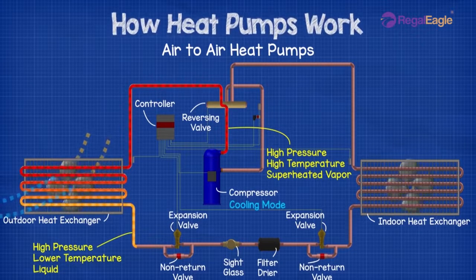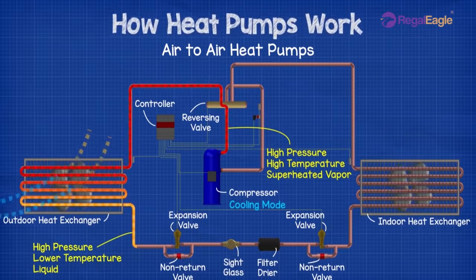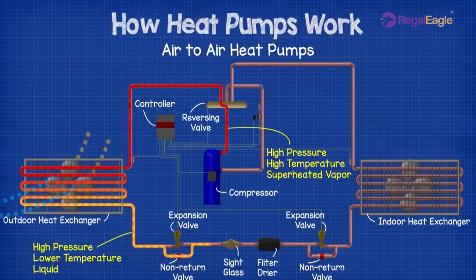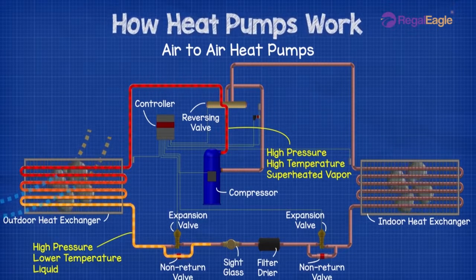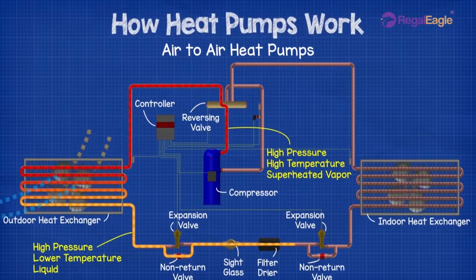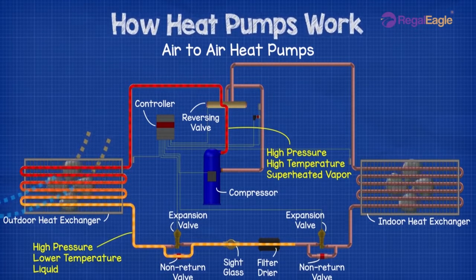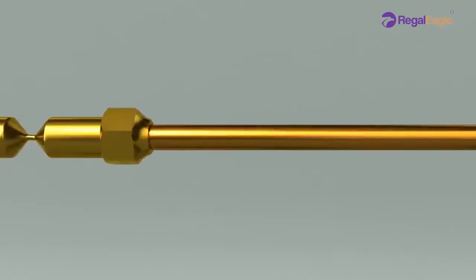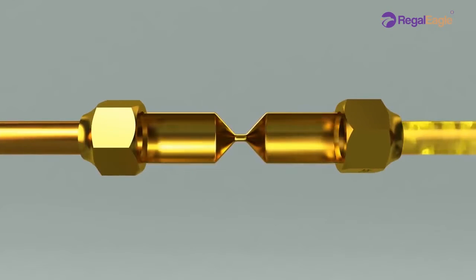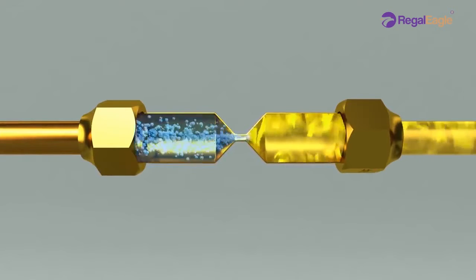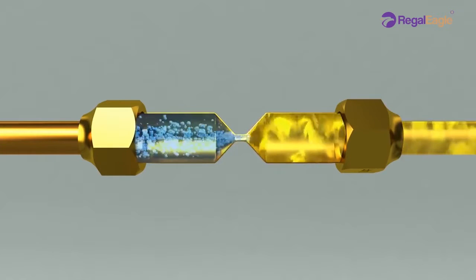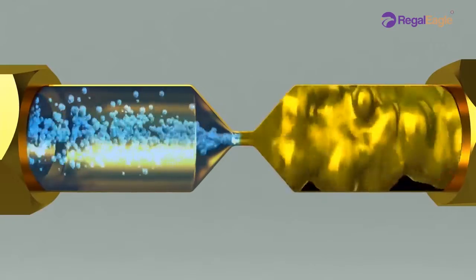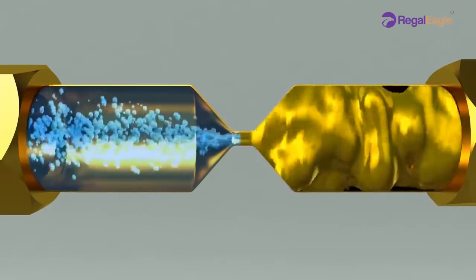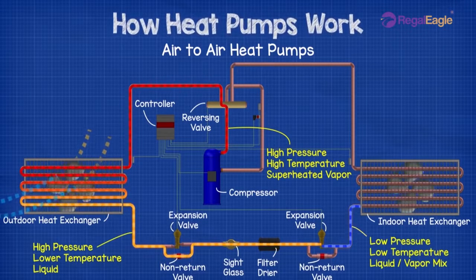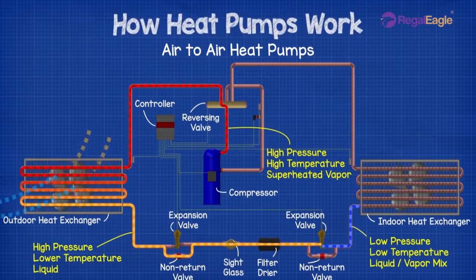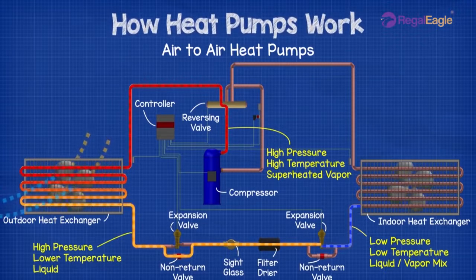The refrigerant leaves as a slightly cooled liquid, and moves through the non-return valve, then the sight glass, and then the filter dryer. The next non-return valve is closed, therefore, the refrigerant passes through the expansion valve. There is a section in the expansion valve with a small diameter. When the refrigerant passes through this small diameter region, it splits into numerous pieces, which causes a pressure and temperature drop. The refrigerant leaves the expansion valve as a low temperature, low pressure, liquid vapor mixture.